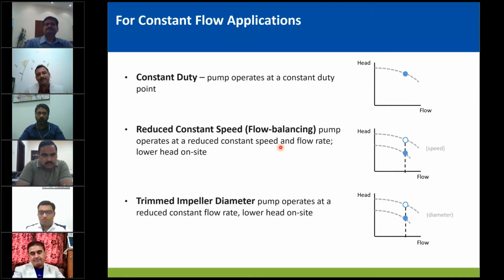Now, later on, when we had variable speed drives in place, we used to install variable speed drives and slow it down to the required point, but it would still be operating towards the lower speed, but towards the right. So we did not know the actual operating point, or the efficiency or the reliability of the pump over a period of time, and it tends to fail when we don't see the best operating points and best practices there.